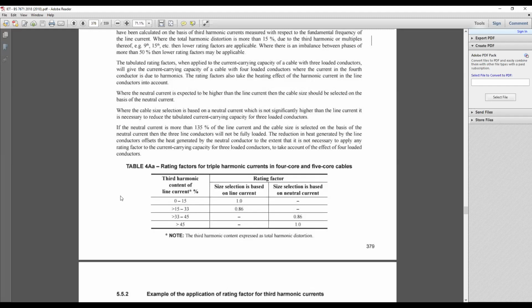So I think you guys can understand this, because 33.33, actually this is 1 over 3, 1 over 3 into 3, it will come to 1, right? So let's say this is 35, so 35% neutral current, 35% third harmonics means in the neutral it will be 35 into 3, that means 105% current. So in that case your neutral current is higher than your line current.